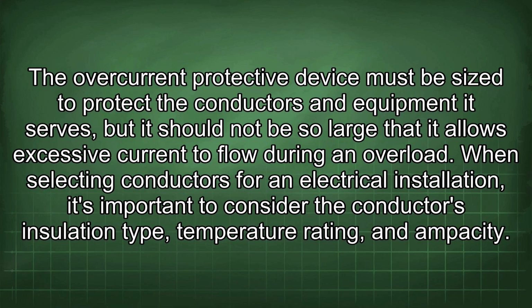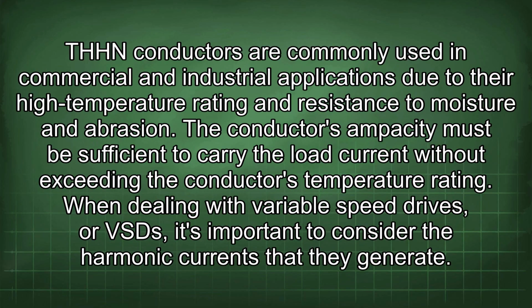When selecting conductors for an electrical installation, it's important to consider the conductor's insulation type, temperature rating, and ampacity. THHN conductors are commonly used in commercial and industrial applications due to their high temperature rating and resistance to moisture and abrasion. The conductor's ampacity must be sufficient to carry the load current without exceeding the conductor's temperature rating.